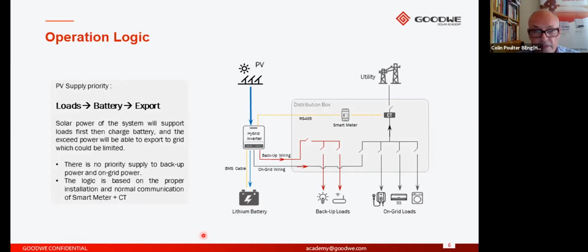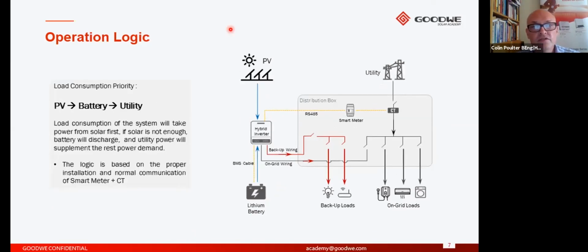Okay, let's now have a look at what happens on the reverse side of things when it comes to discharging the batteries. So let's imagine here we've got this same inverter. We've got a PV supply coming in. It's daylight, and we've got PV power being generated by the inverter. But perhaps the loads within the building at this point in time are just not quite high enough to be met by the output of the inverter. So the CT is going to detect a potential need to draw power from the grid, but it's going to determine the fact that if there's any power in the battery, and if there's any charge capability in here, then to support the load, it's going to start discharging that battery to assist in running all these loads.